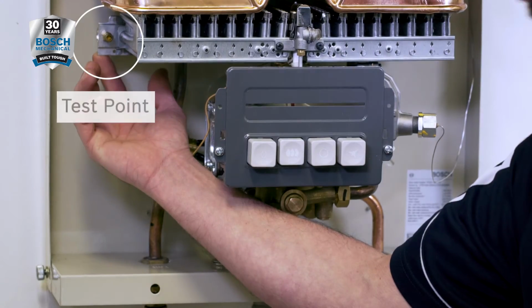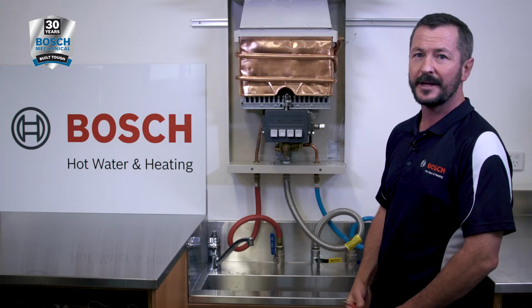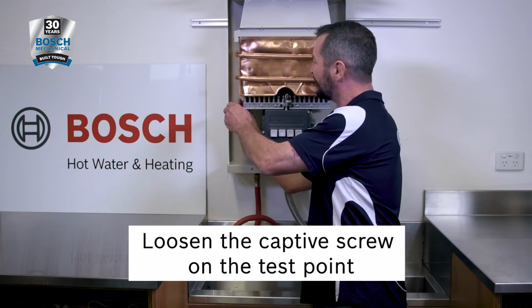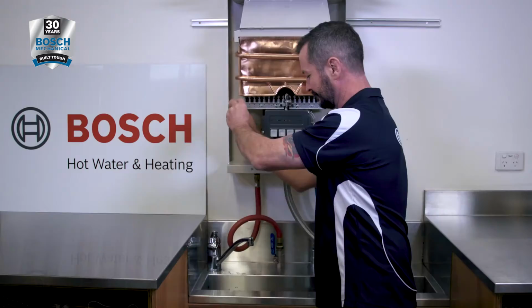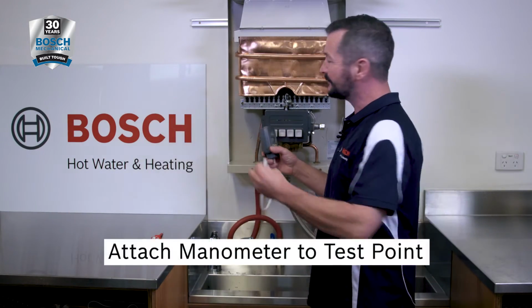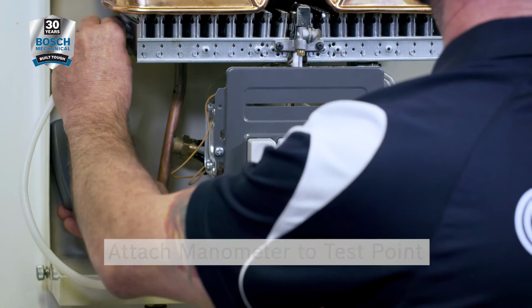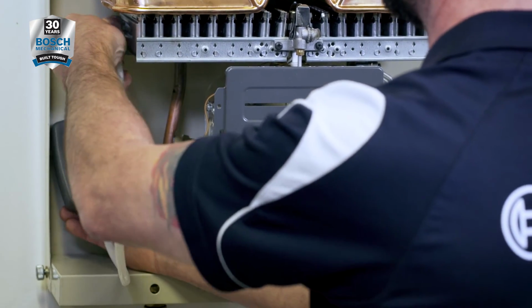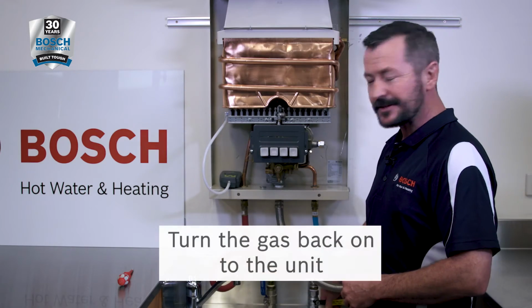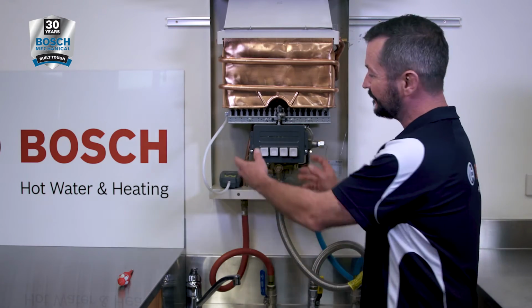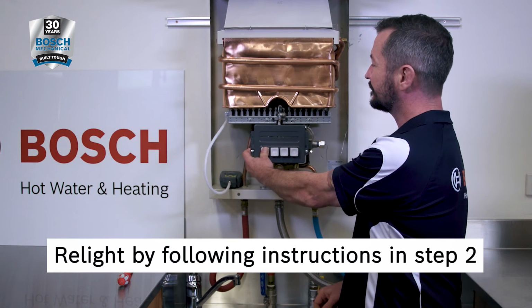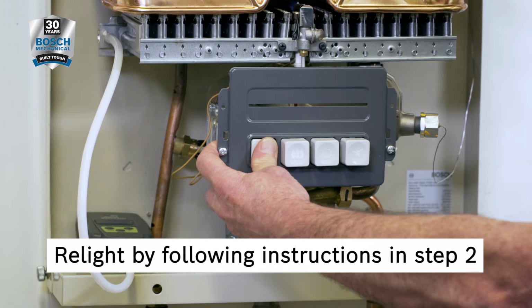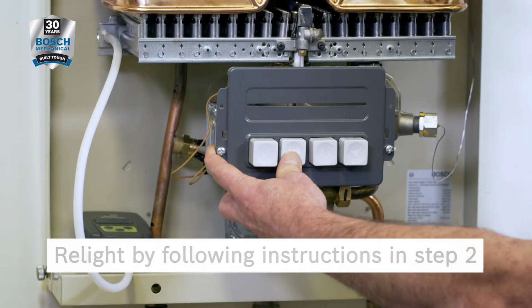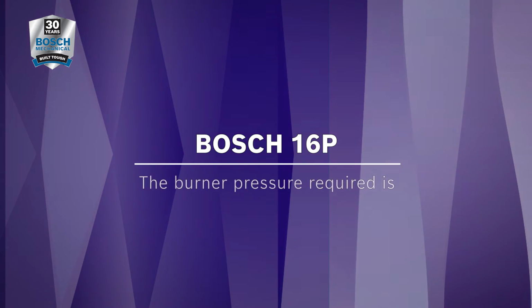Next step is to test the maximum burner pressure. The burner test point is located here on the left-hand side of the burner. Loosen the captive screw of the test point and attach your manometer. Turn back on the gas to the unit and relight the hot water system. Once the unit's relit, we can test the burner pressure.